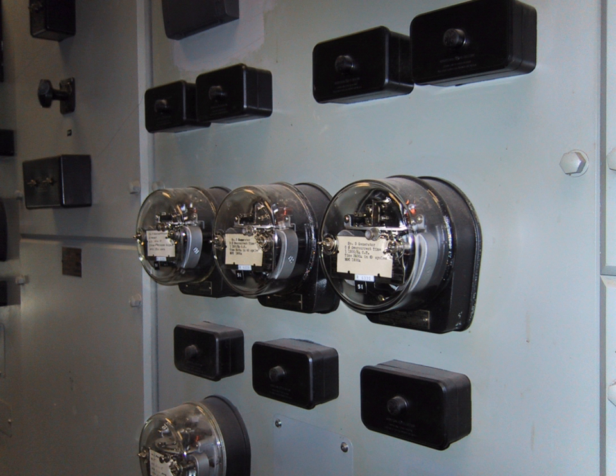Current transformers in a differential scheme must be chosen to have near identical response to high overcurrents. If a through fault results in one set of current transformers saturating before another, the zone differential protection will see a false operate current and may false trip. GFCI ground fault circuit interrupter circuit breakers combine overcurrent protection and differential protection, non-adjustable in standard, commonly available modules.